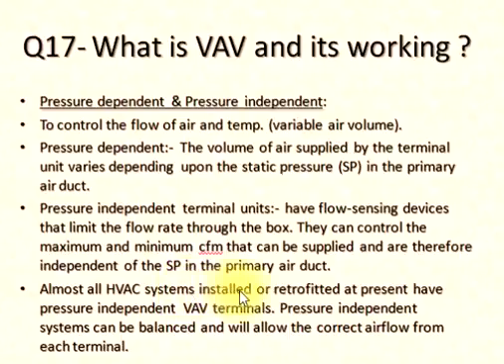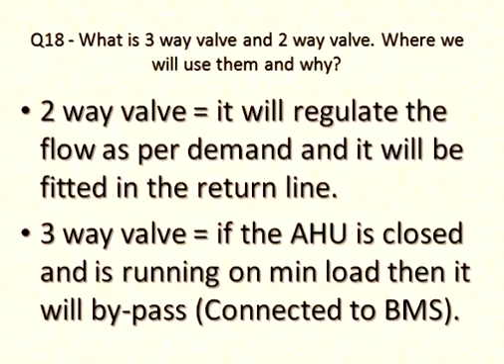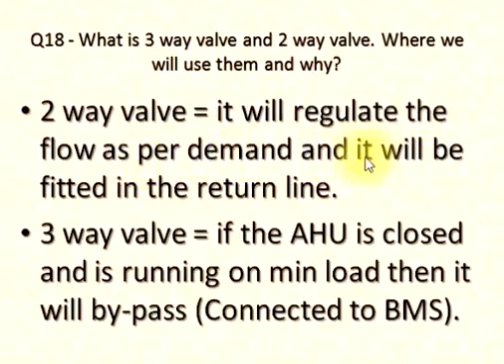Almost all HVAC systems installed or retrofitted at present have pressure independent VAV terminals. Q18: What is a 3-way valve and a 2-way valve — where and why do we use them? 2-way valve: it regulates the flow as per demand and is fitted in the return line. 3-way valve: if the AHU is closed and running on minimum load, it will bypass — connected to BMS.